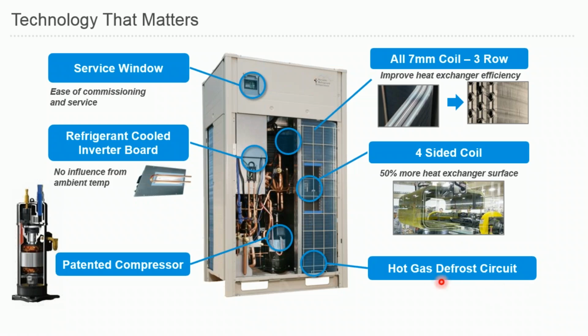Your hot gas defrost circuits, which allow the bottom side of the heat exchanger to act as a condenser throughout the year, will still be there. Whatever heat gain you're getting through that dedicated refrigerant circuit next to the inverter board will be dumped into that bottom circuit. So it will reduce the complexity that you see in the cold climate application with additional electric heater kits and whatnot. Another major addition in terms of components is the K-type vapor injection scroll compressor that we use in our VRV Aurora and water-cooled T-series models. That is becoming our standard compressor design for 4X heat recovery as well.